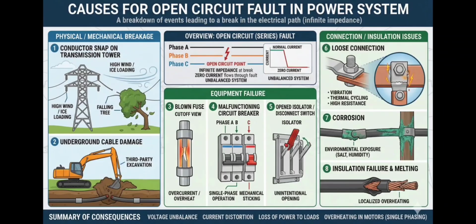And similarly, the isolator. In a power system, if we have to do any repair or maintenance for a particular circuit, first we usually isolate the electric circuit using this isolator, and after the repair or maintenance, we close the isolator. During the closing of the isolator, if the contacts are not properly connected and if any air gap is left between them, it will create an open circuit, and this will lead to an open circuit fault.